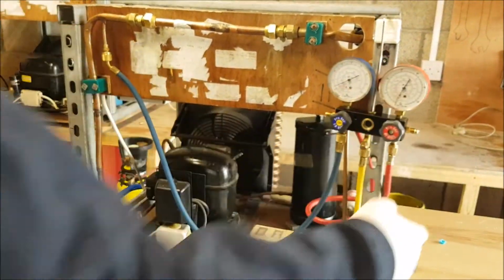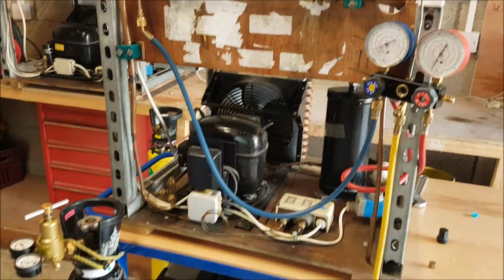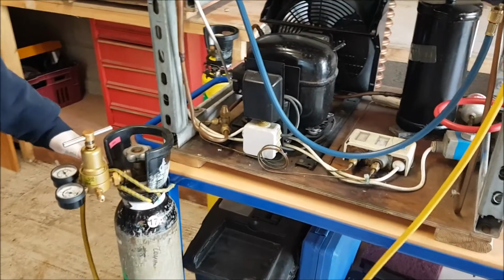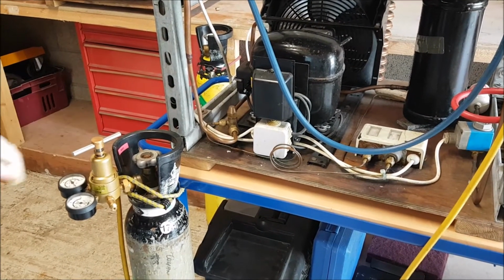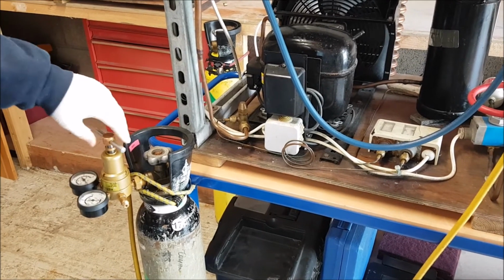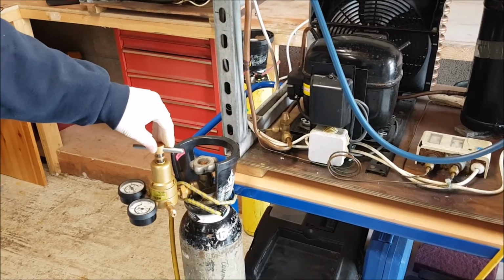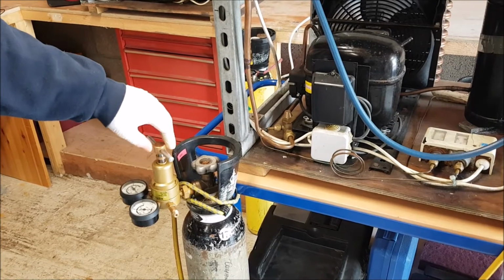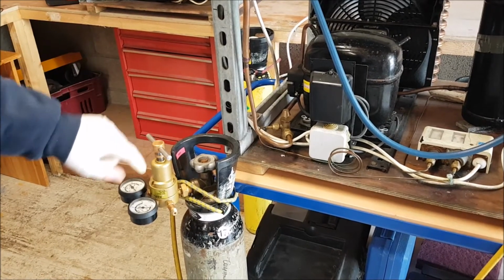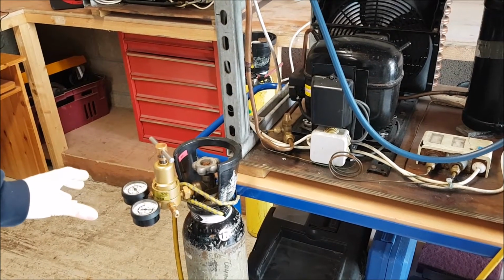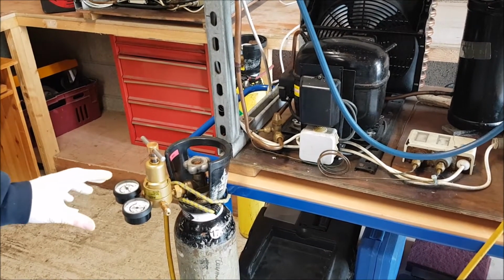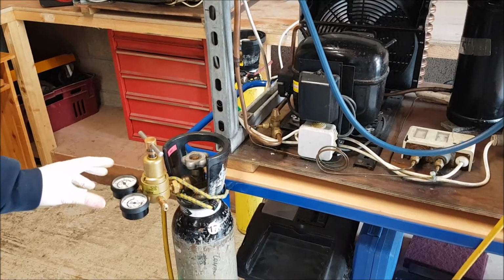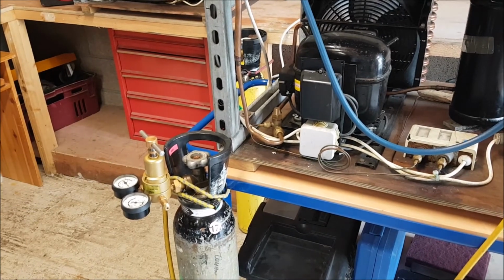Okay, so we get our service line from our manifold. We connect our service line to our nitrogen bottle, and again we have to be very careful with nitrogen. This is my nitrogen regulator and I have it loosened as much as possible, so basically you're going to have it anti-clockwise. You've got to make sure that when we open this bottle we don't have a surge of pressure going through. On a new bottle, it could be as high as 200 bar pressure.